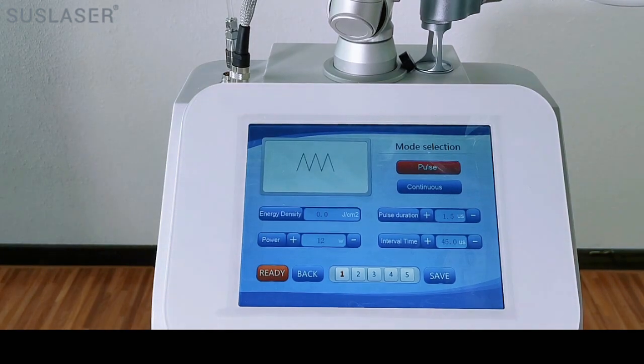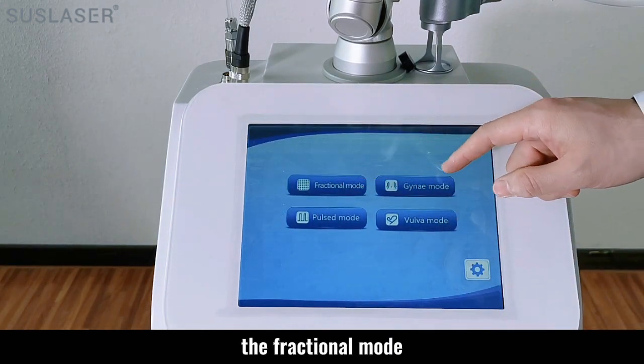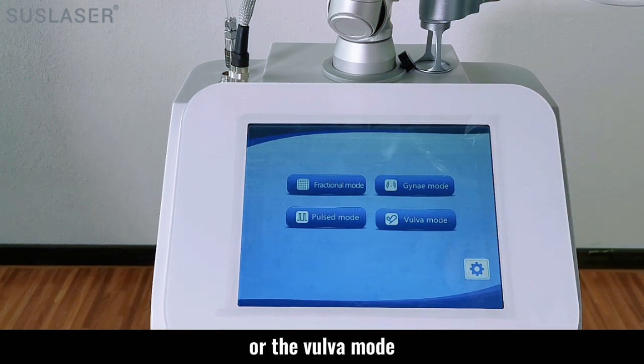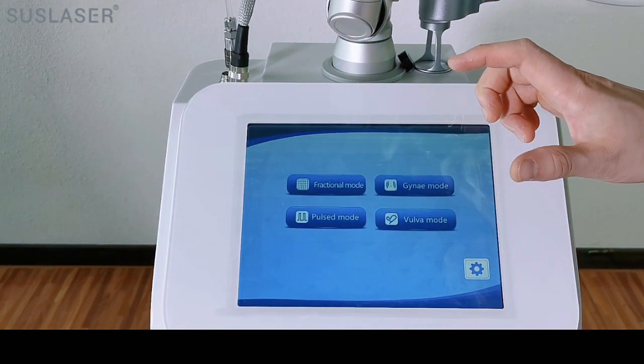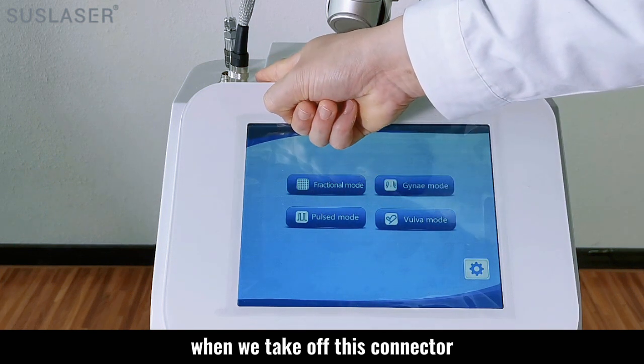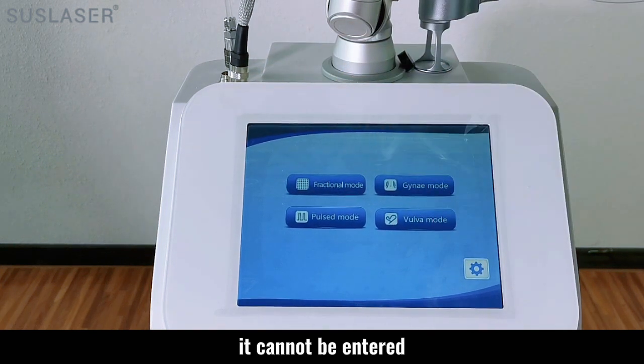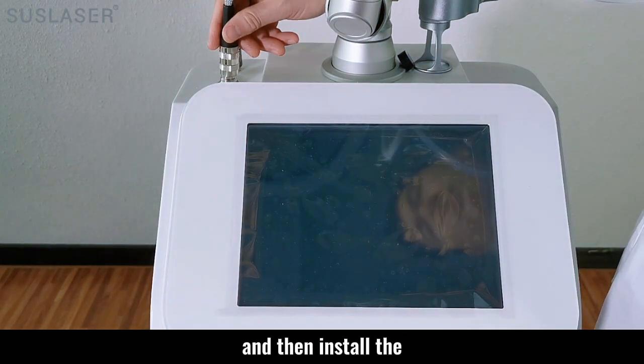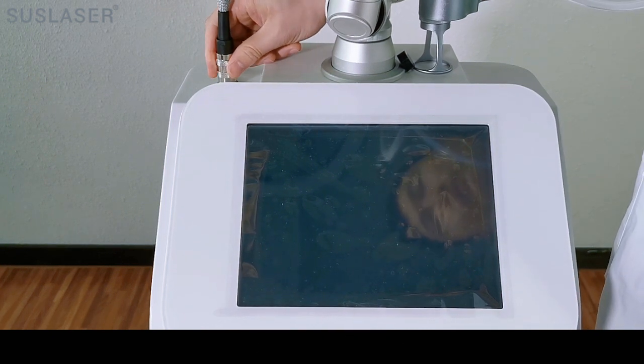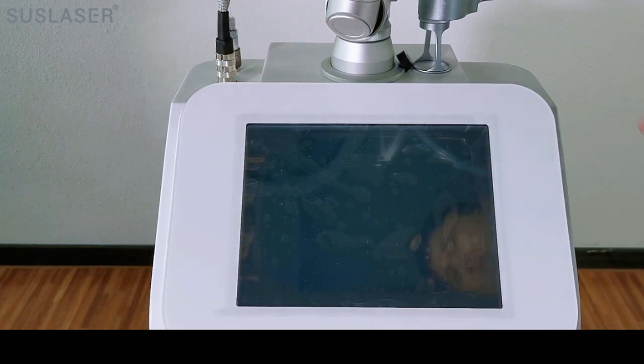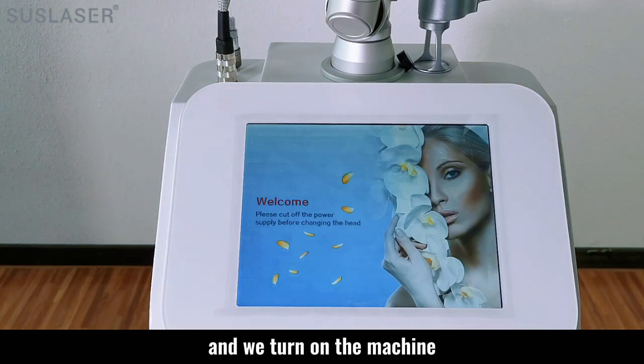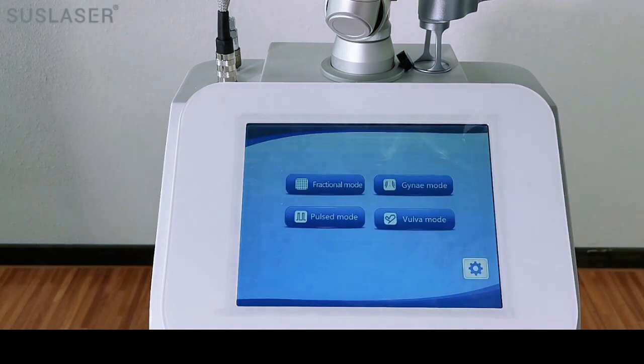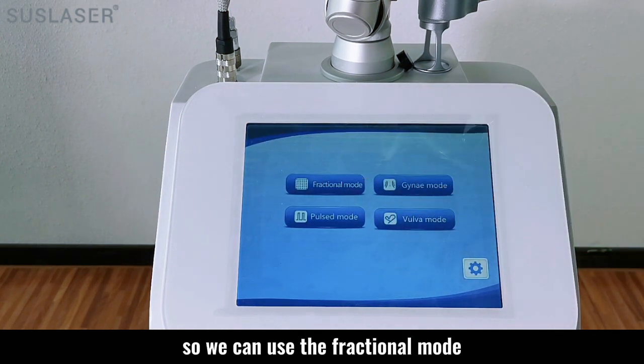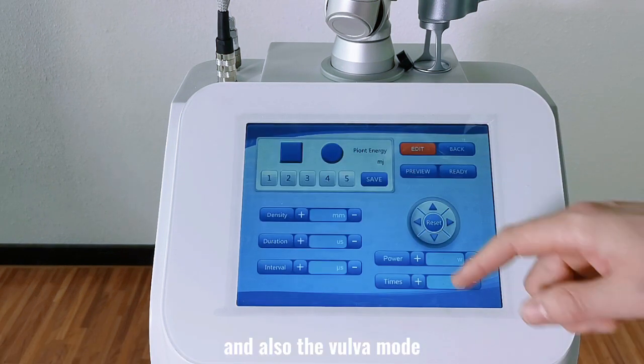And after using the pulse mode, if we want to use the fractional mode, gynecology mode, or the vulva mode, as we can see, when we take off this connector, it cannot be entered. So we need to turn off the machine and then install the connector back. And we turn on the machine. So we can use the fractional mode, gynecology mode, and also the vulva mode.